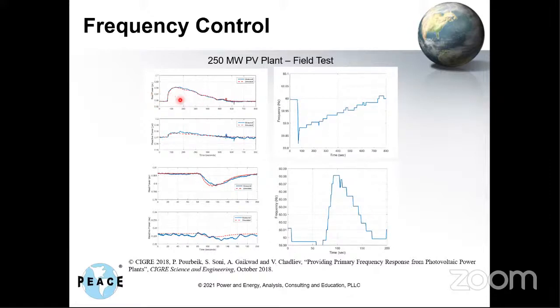And you see this is megawatts - they increased and then came back as the frequency recovered, so you had primary frequency response. Then here, the frequency was played in to simulate frequency increasing, and you see megawatts dropped and then came back. So you can have frequency response.